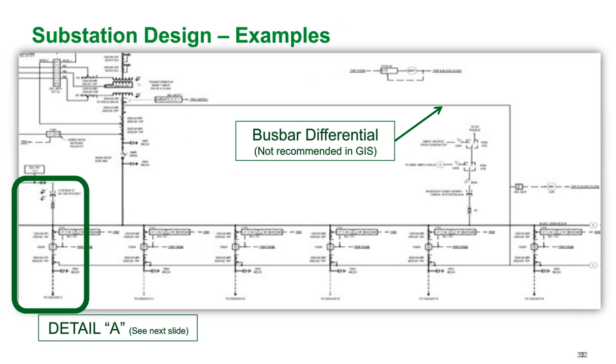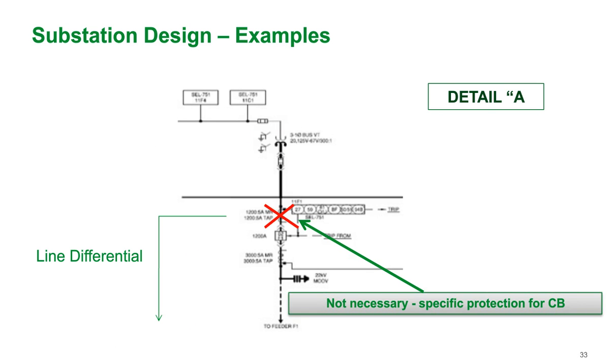So here, bus bar differential, of course, and then eliminating that overlapping protection of the circuit breaker, because the only failure point in there is a vacuum interrupter, which is a highly reliable component in GIS.